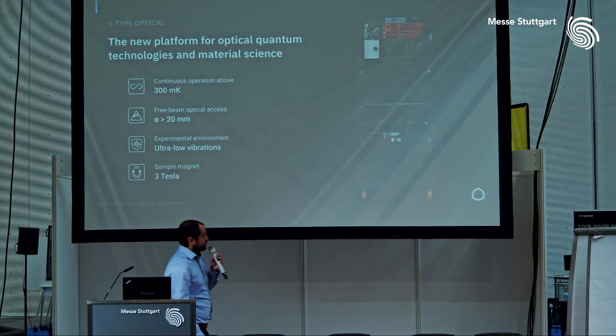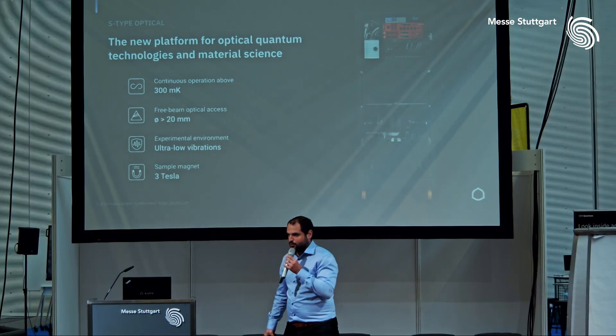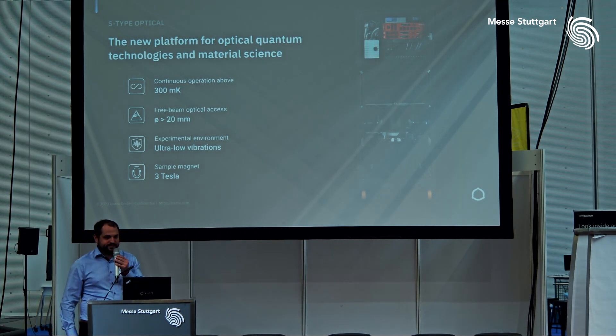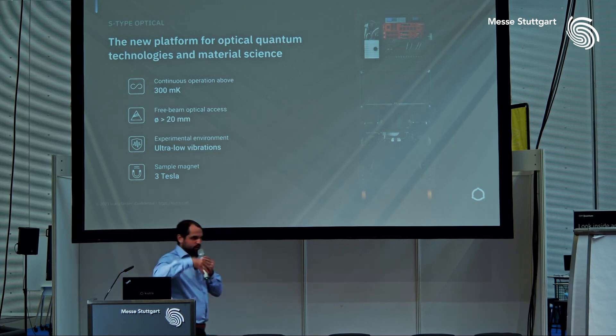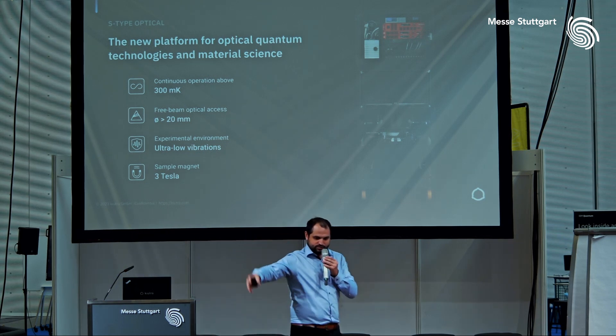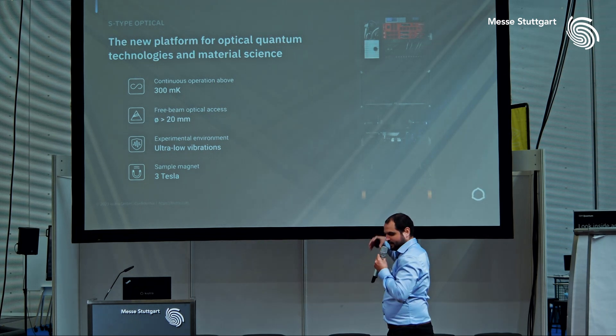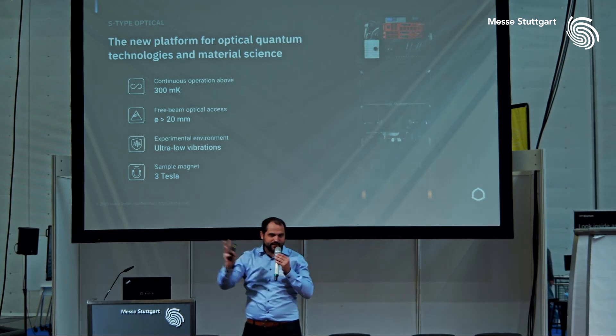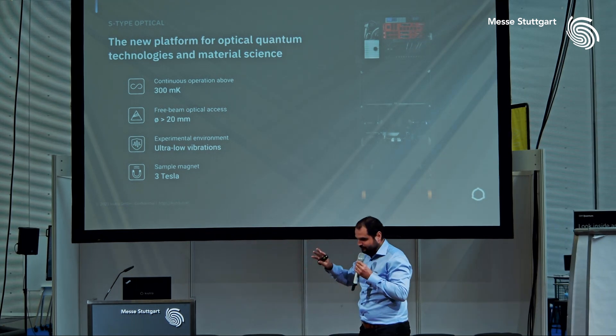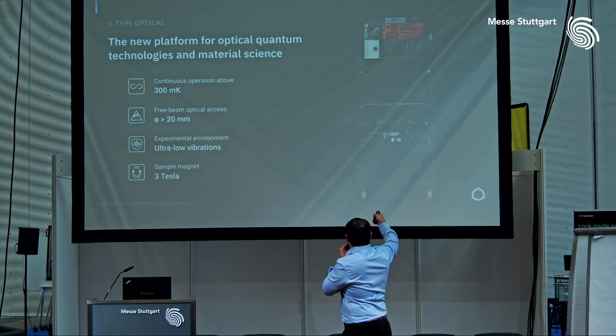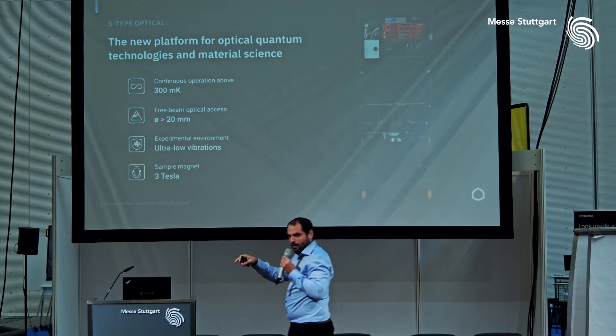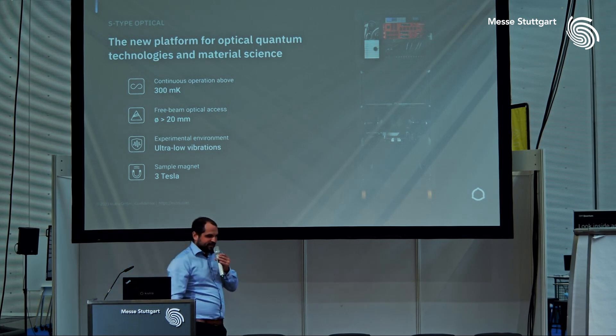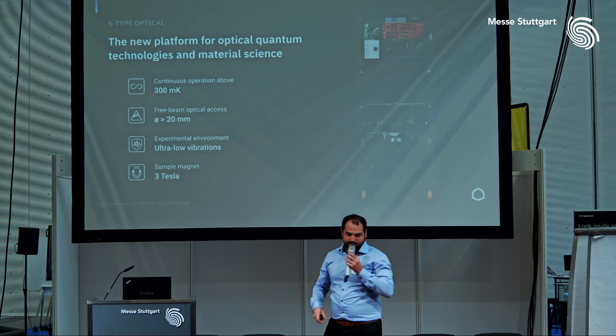This year we also delivered two units of our new system, the S-Type Optical. It's based on the same cooling technology, providing continuous sub-Kelvin operation with ADR technology. But instead of having the fast sample loader on top, we packed it very tightly in a 19-inch rack and allowed optical access at the top, making it a platform for optical quantum technologies and material science.